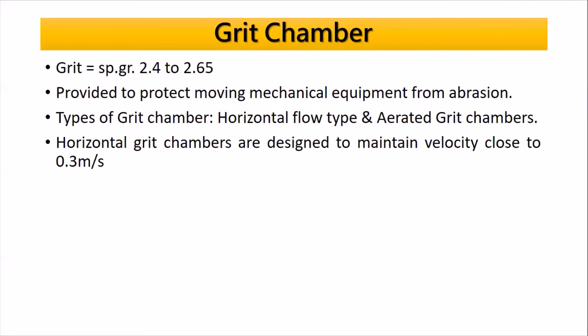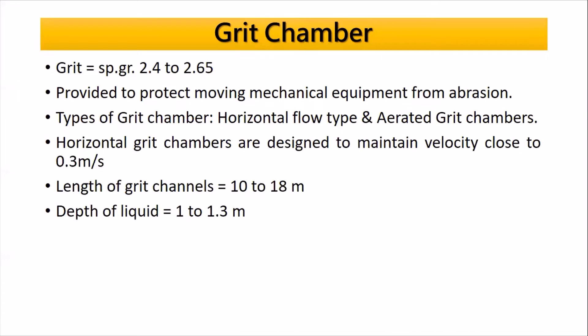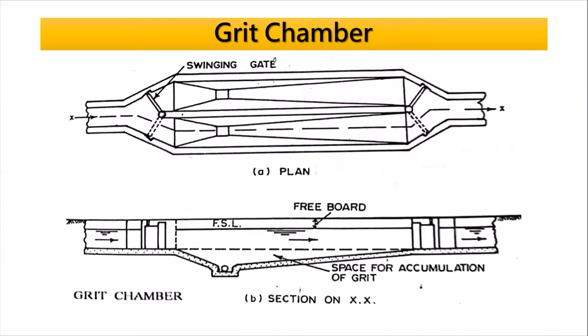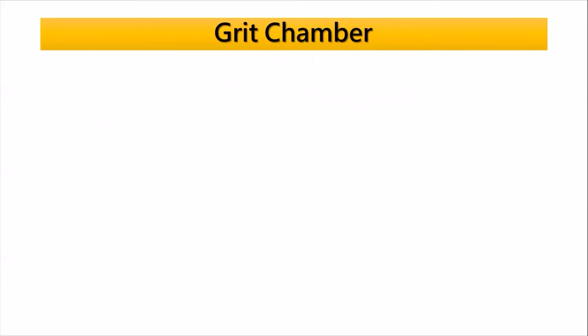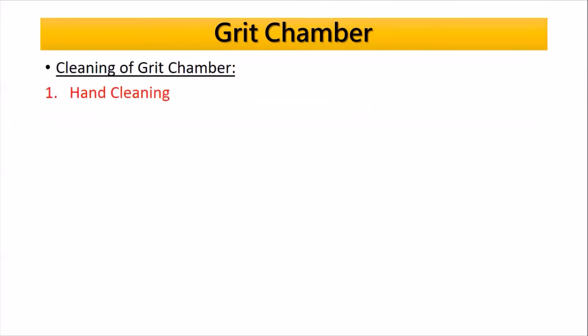Horizontal flow grit chambers are designed to maintain the velocity close to 0.3 meters per second. The length of the grit channel is 10 to 18 meters, and the depth of liquid is 1 to 1.3 meters. This is a diagram showing the plan and section of the grit chamber.